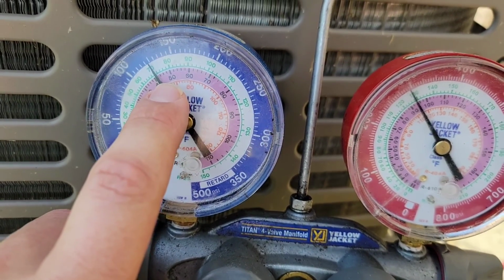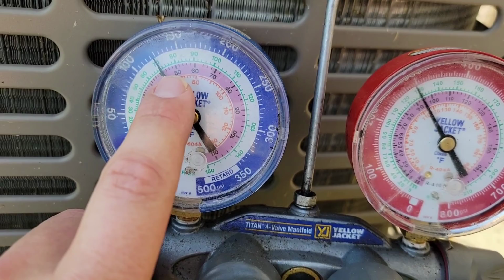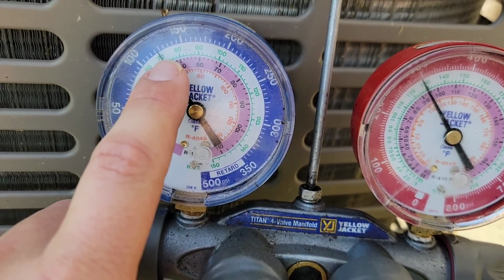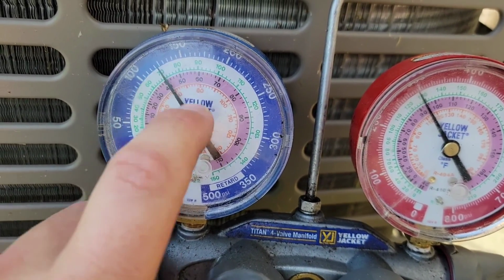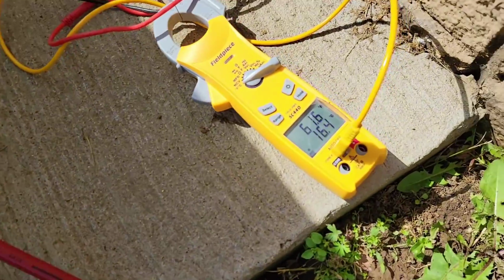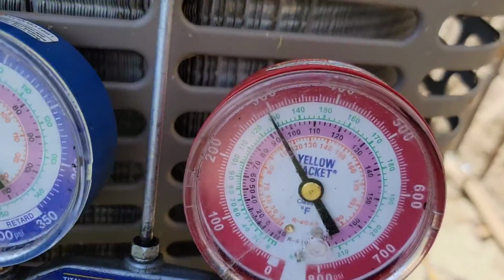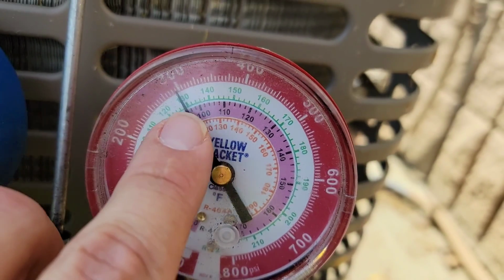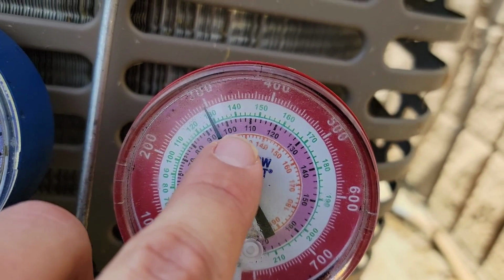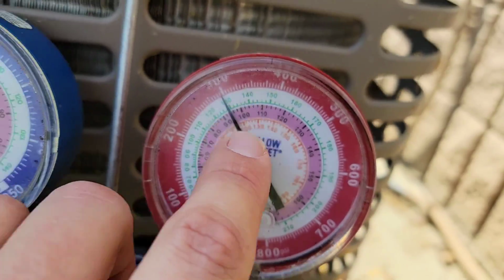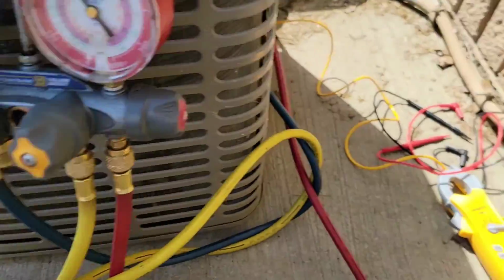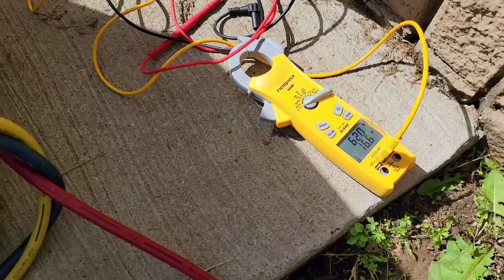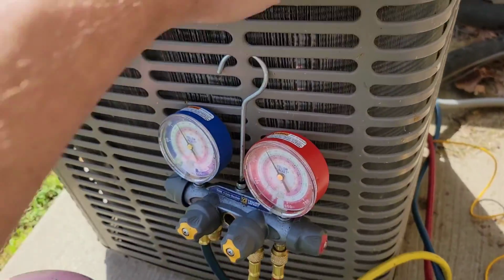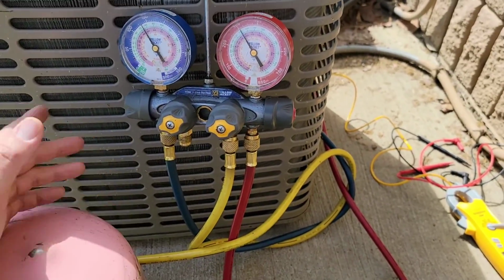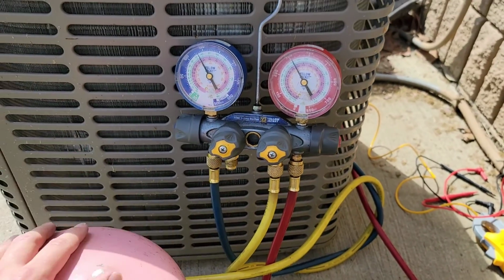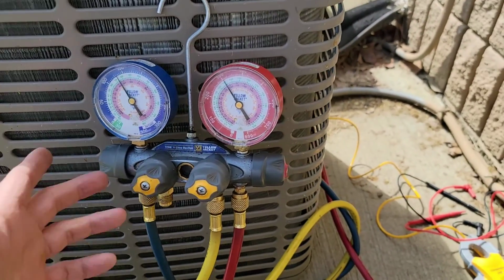See, it's 125 now, but because we have a different indoor temperature, it's a little hotter, we need to get it up here, maybe about 135, 145, and it'll be charged. That temperature there will drop. Head pressure is already pretty high, 300, but we're going to be a little bit higher by the time this ends, probably about 325. All right, let's add some refrigerant and see how that suction temperature changes. 410A, sometimes it takes a pound, sometimes it takes 2 or 3 pounds. Make sure you have scales to weigh your refrigerant so you know how much you're putting in.